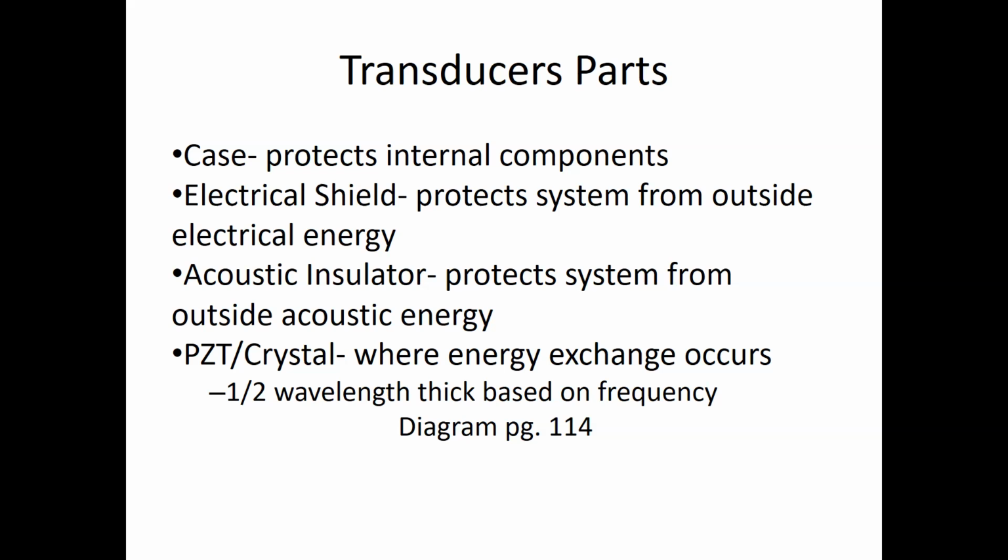So I'm up in the portable ICU unit and I've got, you know, the ventilators on. There's these things that compress legs that are on. I have all these electrical things going on. So I need to be able to insulate my transducer from receiving outside electrical impulses. And then we also have an acoustic one. Not that you would yell into your transducer and have it do anything, but if there's an acoustic impulse that's coming in and going to affect those crystals, that will result in an erroneous reading. So we want to make sure that we're insulated from both of those things.